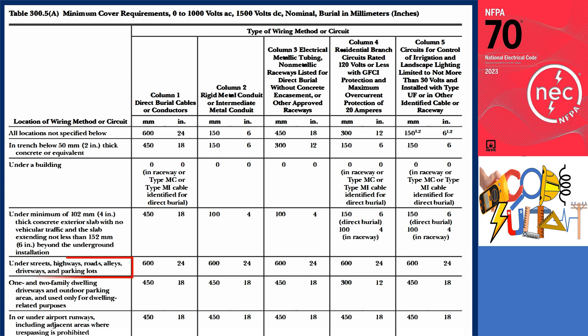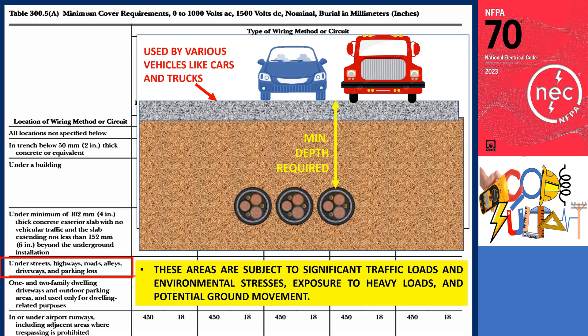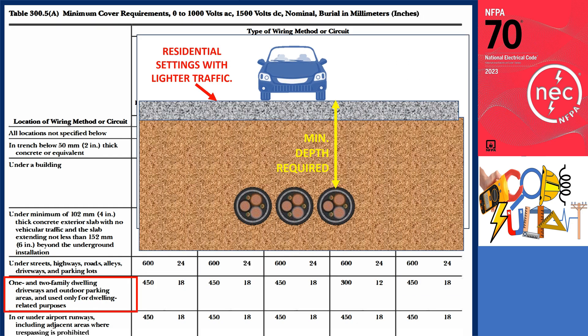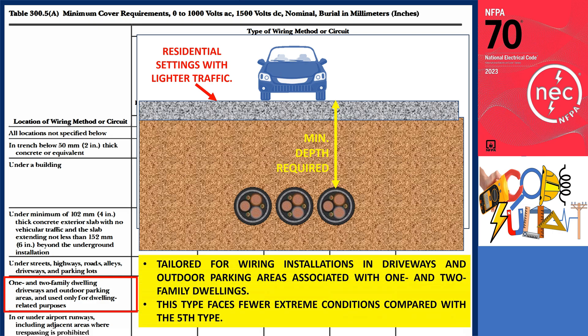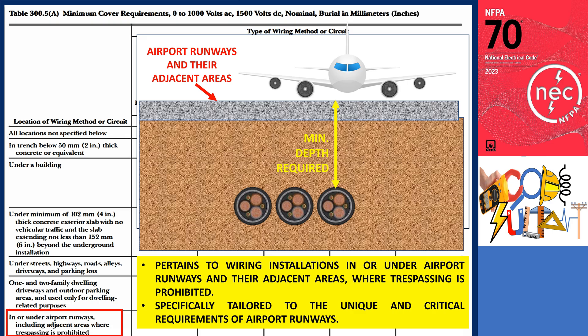The fifth location type encompasses wiring installations beneath streets, highways, roads, alleys, driveways, and parking lots — areas subject to significant traffic loads, environmental stresses, heavy loads, and potential ground movement. The sixth type is specifically tailored for wiring installations in driveways and outdoor parking areas associated with one and two family dwellings, facing fewer extreme conditions than type five. The seventh type pertains to wiring installations in or under airport runways and their adjacent areas where trespassing is prohibited, with specific safety and regulatory implications. Type 7 is tailored to airport runways while type 5 addresses urban traffic scenarios.